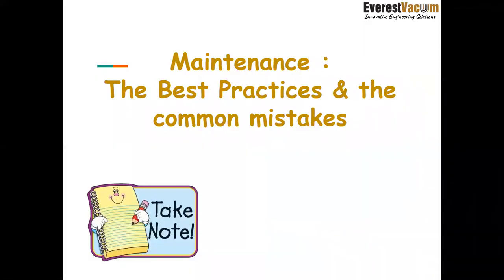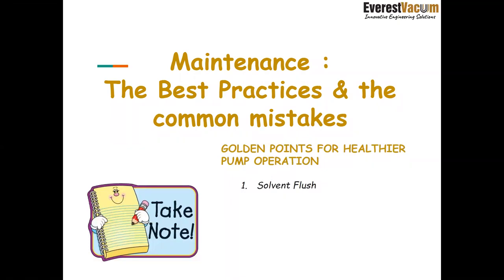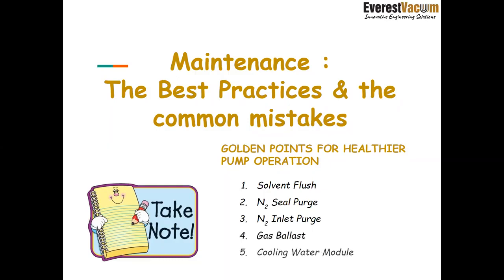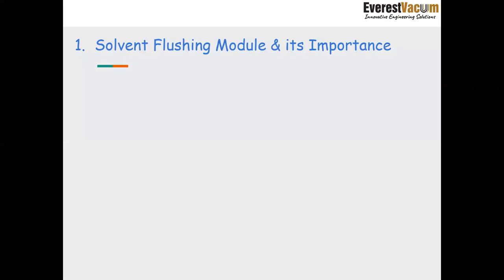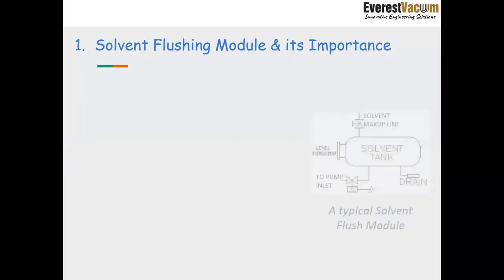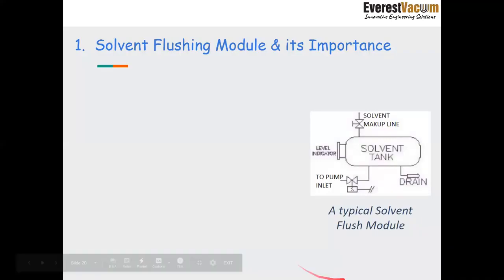Now coming to the maintenance parts, the best practices and the most common mistakes, these are the golden points for healthier pump operation. It is solvent flushing, N2 seal purge, N2 inlet purge, gas ballast, and cooling water module. I'll be covering all these modules one by one because they are very, very critical for the health of the machinery. So first, it is the solvent flushing module and its importance. This is how the solvent flushing module looks like.